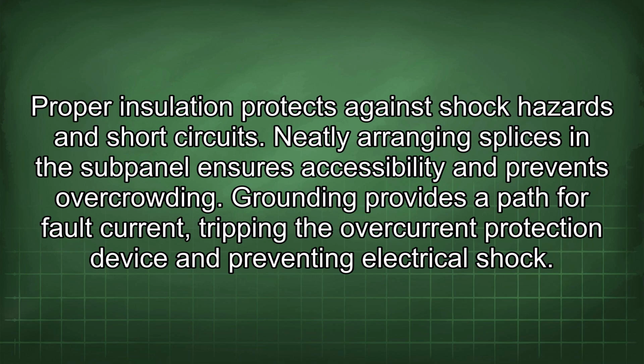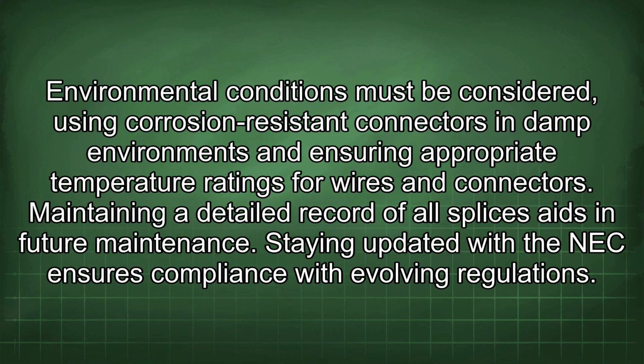Grounding provides a path for fault current, tripping the overcurrent protection device and preventing electrical shock. Environmental conditions must be considered, using corrosion-resistant connectors in damp environments and ensuring appropriate temperature ratings for wires and connectors.